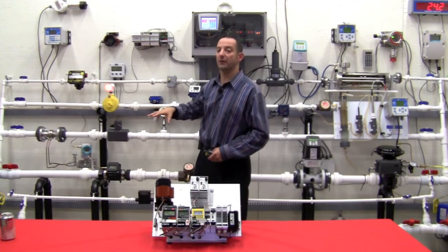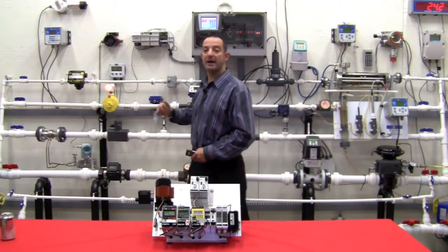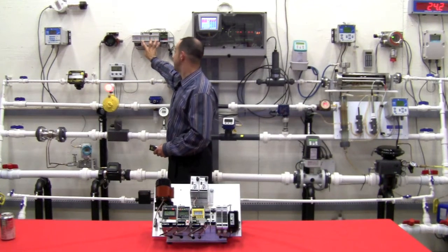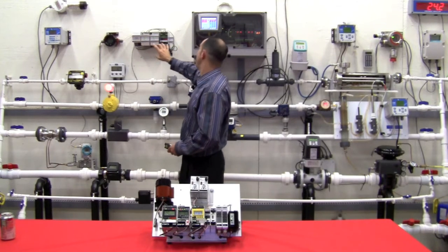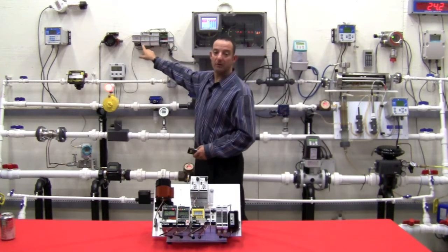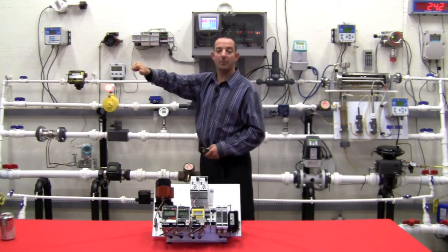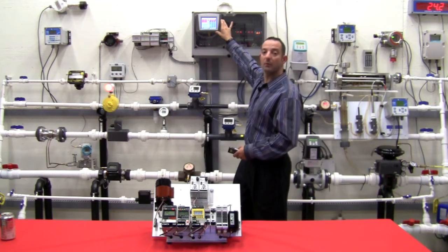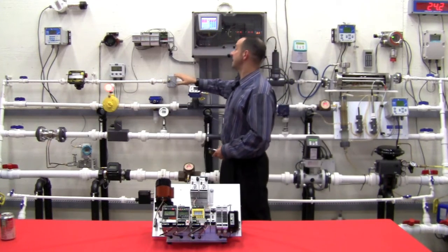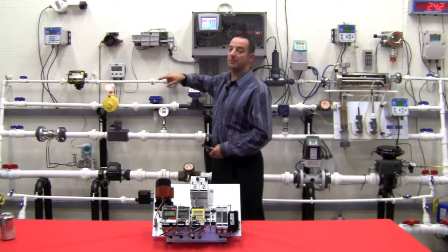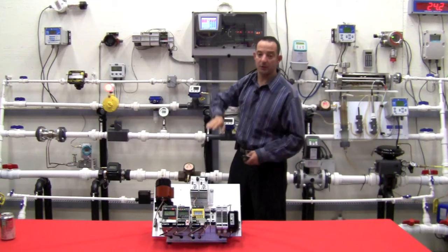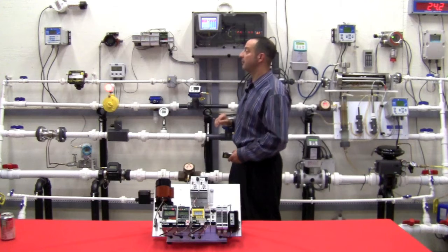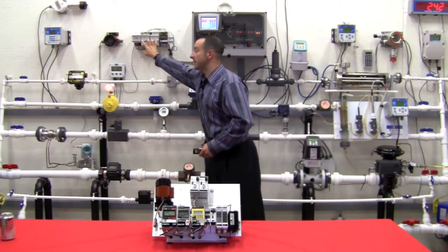A peer-to-host configuration would involve a control system like we have here in the Flow Lab, where I'm bringing in my signals here through analog and temperature input modules, and through Modbus protocol, either over twisted copper wire or a piece of Ethernet cable, I'm reading those signals with a controller, with a Modbus driver. In this case, the Moore Industries net concentrator system acts as remote I/O for the control system. Most modern control systems have no trouble reading Modbus data, and that's the protocol that we've settled on here.